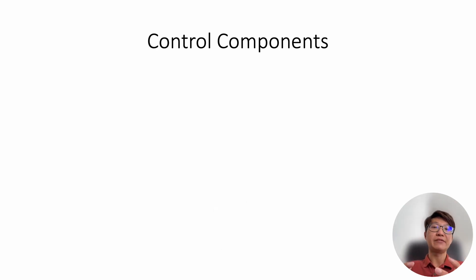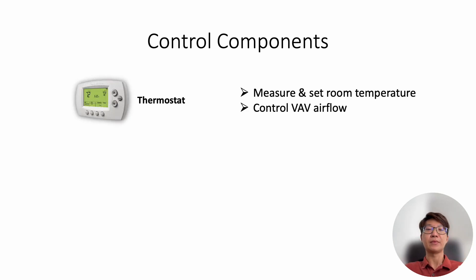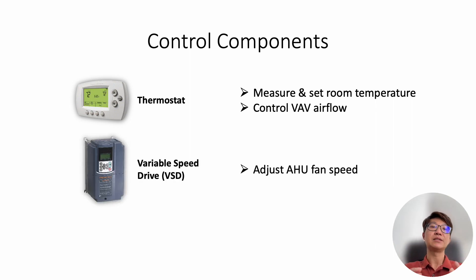So in order for VAV box to know how much airflow it wants to allow it to pass through, we need some control components. So the first control component is the thermostat. Thermostat is located inside a room. Then it is used to measure the current room temperature. And also it is used to set the room temperature. You can actually set how much temperature you want to maintain inside a room. So when the temperature deviated from there, then the thermostat will send a signal to the VAV to ask the VAV to either increase the airflow or reduce the airflow.